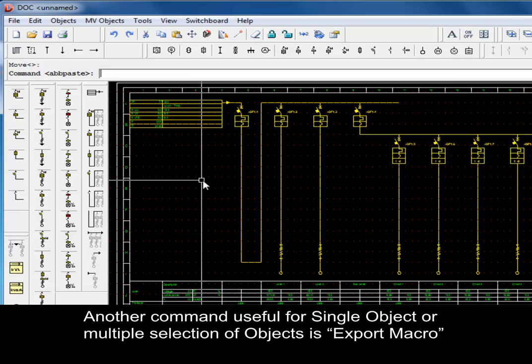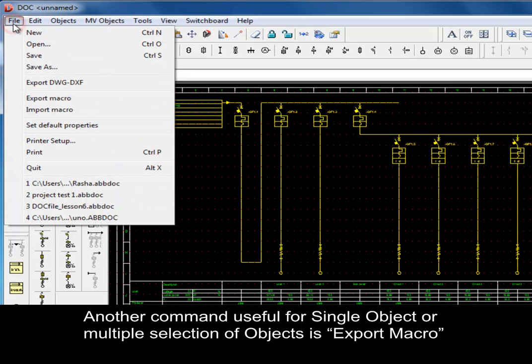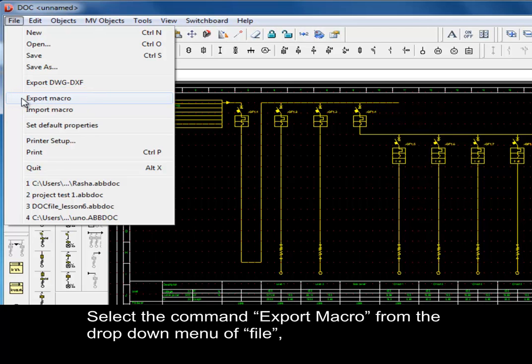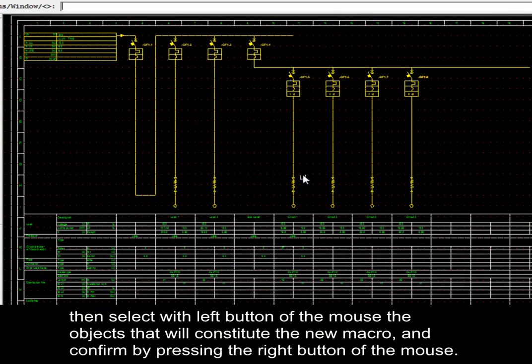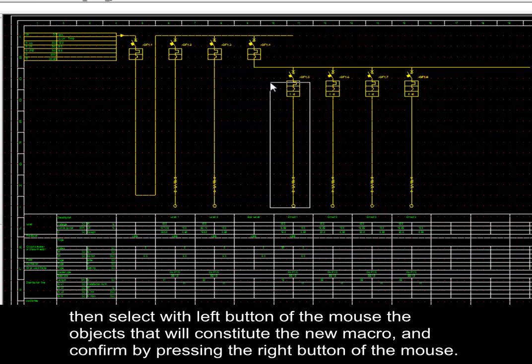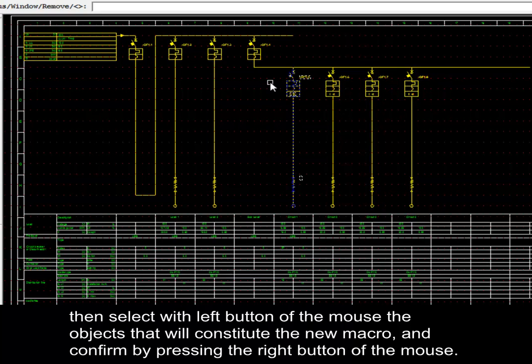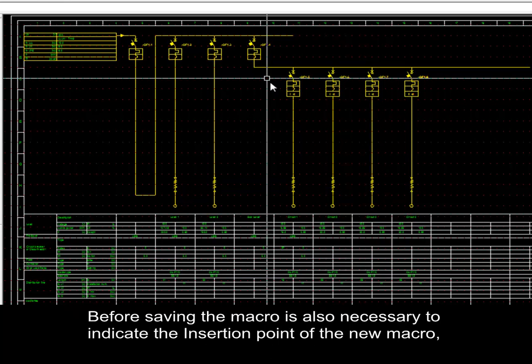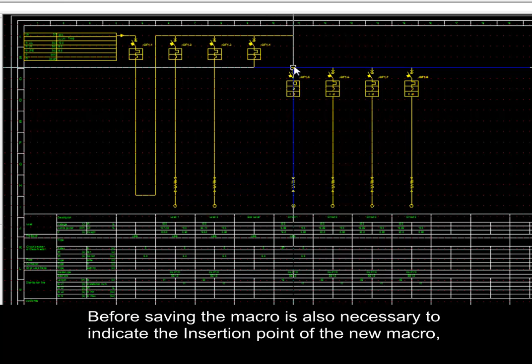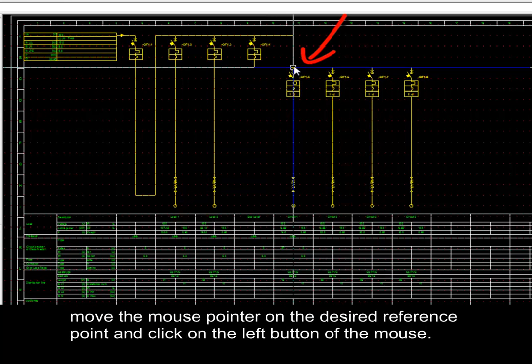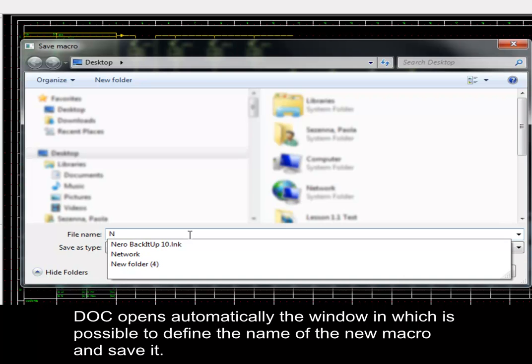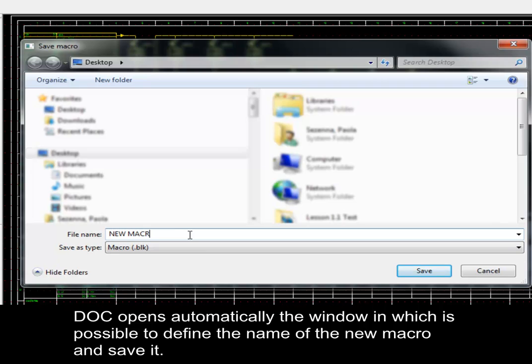Another useful command for single or multiple objects is Export Macro, which allows creation of a macro saving all predefined characteristics. Select Export Macro from the File menu drop-down, then select the objects that will constitute the new macro with the left mouse button and confirm by pressing the right mouse button. Indicate the insertion point of the new macro by moving the mouse pointer to the desired reference point and clicking the left button. A window opens automatically to define the name of the new macro and save it.